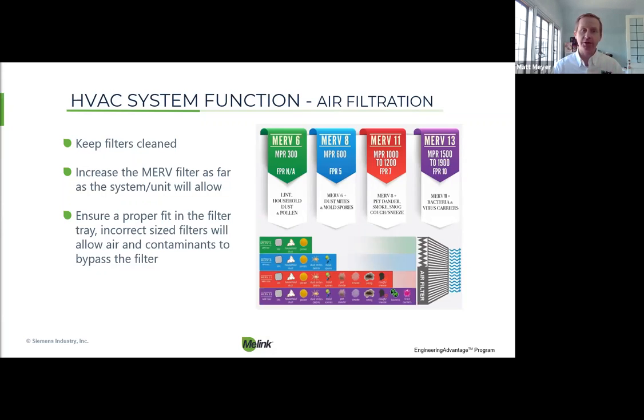The next line is ensuring the proper fit of your filters. This seems like a no-brainer, but being a test and balance firm that Melink is, you'd be surprised at the number of jobs we go to, and the filters are just loosely in there. A maintenance personnel has literally just stuffed in whatever size filter they could find. And without having that whole filter tray filled up from end to end, top to bottom, you're just allowing air particles to move around the filter. Of course, you're going to get some to go through the filter, probably most of it, but you're still allowing contaminants to go around that filter, which is definitely not what you're looking to do, especially during COVID-19. So anyway, next slide, please.